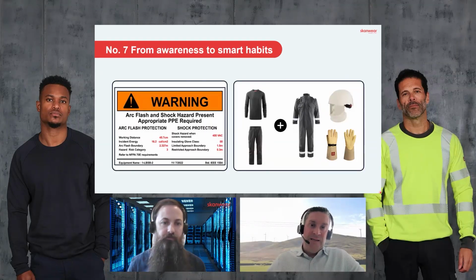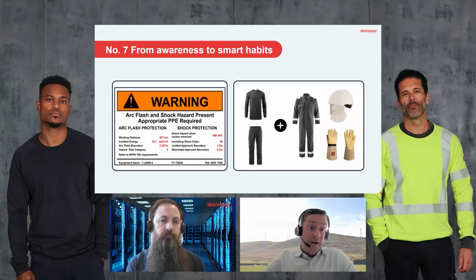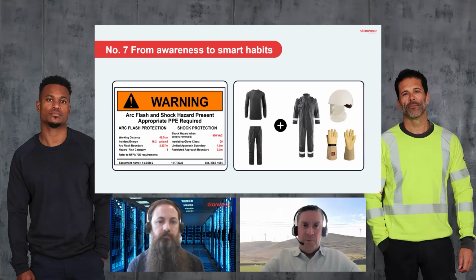So again, this is more label specific for the actual panels. So you're basically putting your warning label on there. So it's an IEEE 1584 requirement for the labeling. Also, labels are listed in NFPA 70E and CSA Z462, but you've got things like working distances on there, incident energy, arc flash boundaries, hazard risk categories. Generally speaking, hazard risk categories are frowned on when you've already got an incident energy, because you should go by the incident energy rather than the risk category.